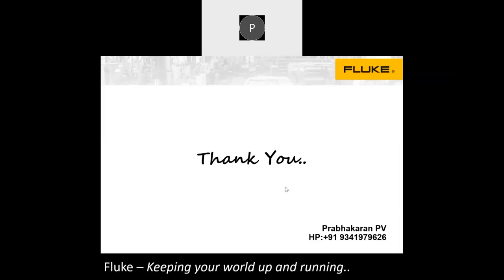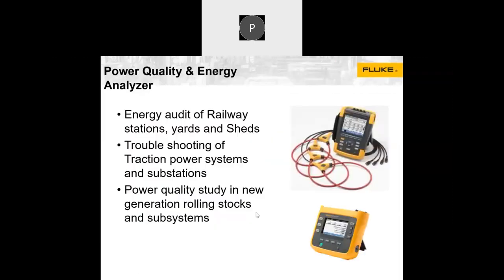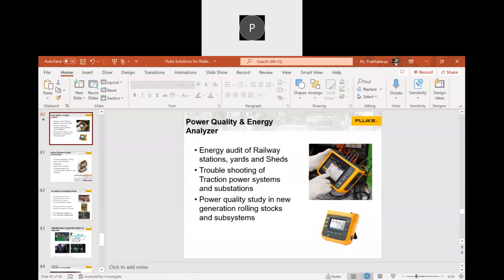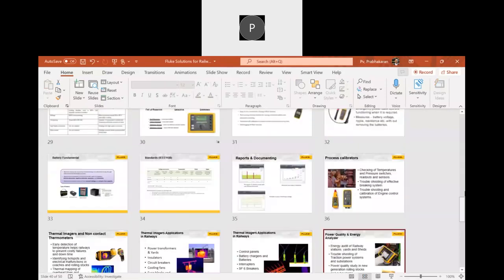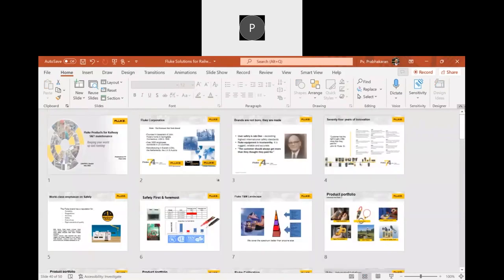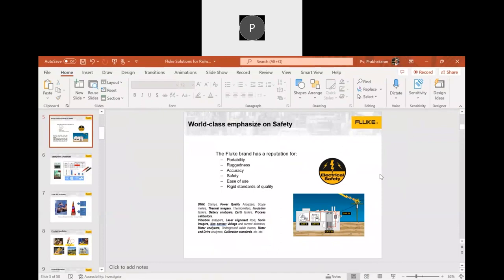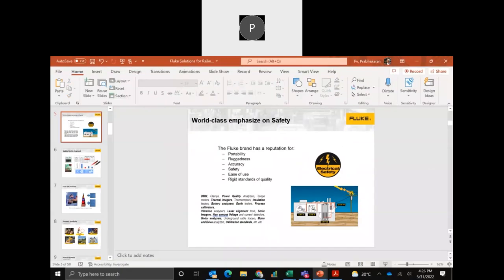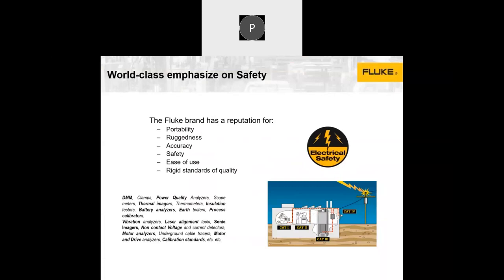If you look at the first few slides, you'll see the category rating is basically the safety rating of devices. Any equipment as per IEC 61010, which is the safety standard, any equipment meant for electrical voltage or current measurement needs to be tested, designed, and certified for electrical safety.